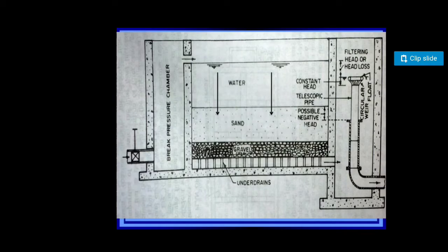So in the slow sand filter, both filtration with the filter media, eliminating the larger particles over the surface of the filter media, retaining them, and letting particles smaller than the pores of the filter media pass through to the effluent section. And then the Schmutzdecke is produced, and the Schmutzdecke has microorganisms. These microorganisms start to disintegrate the organic material into simpler forms like water and carbon dioxide, etc.